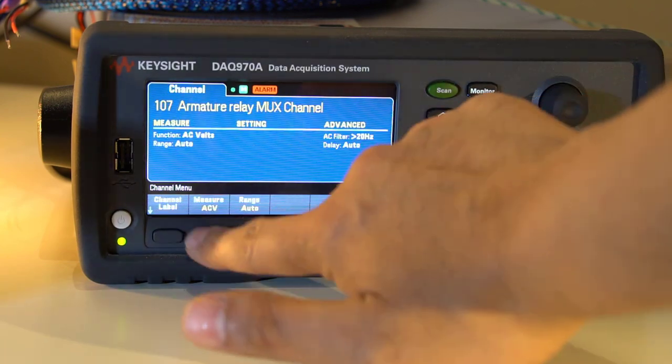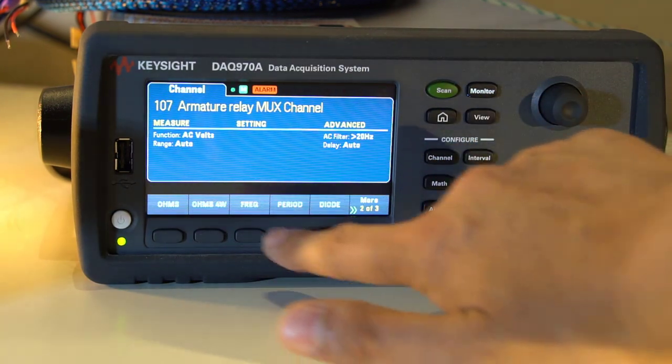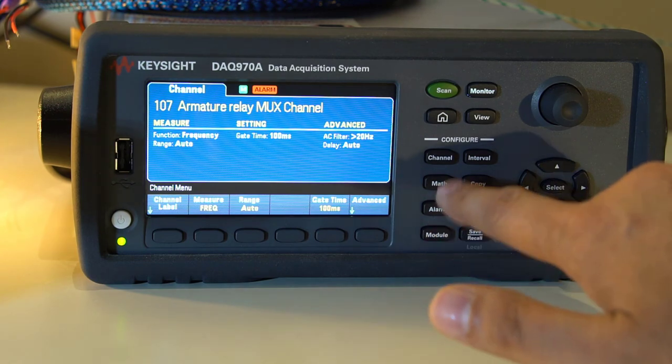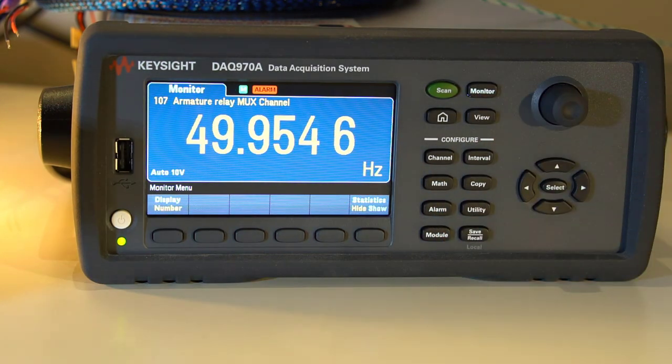It will also measure voltage, resistance including four wire for low ohms, current, capacitance and frequency up to 300 kilohertz.